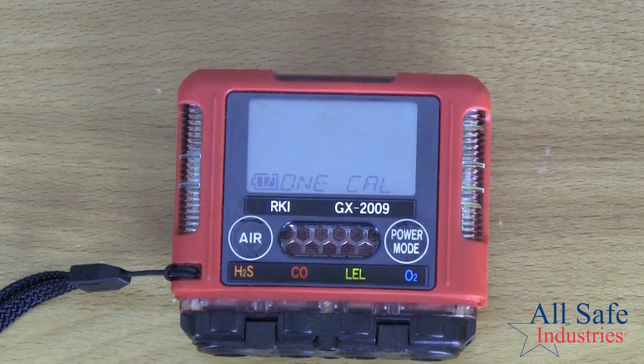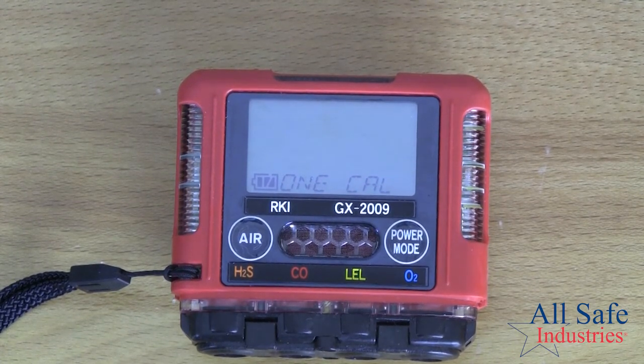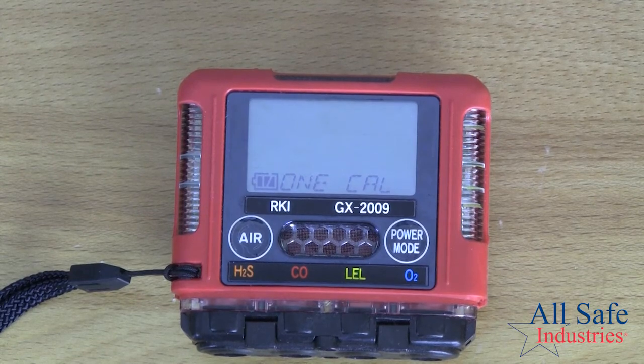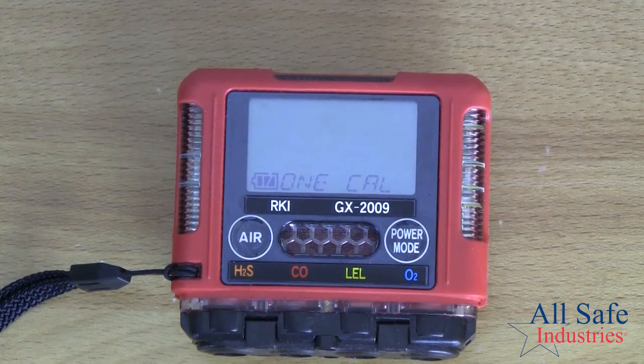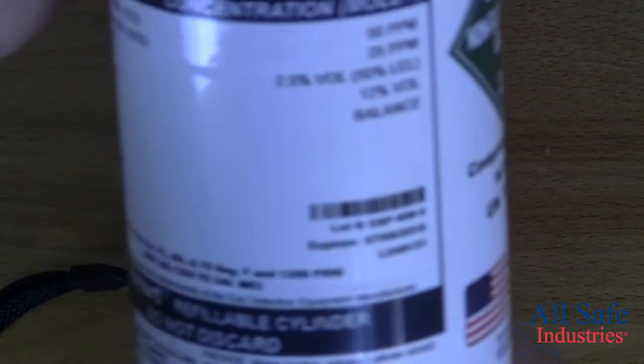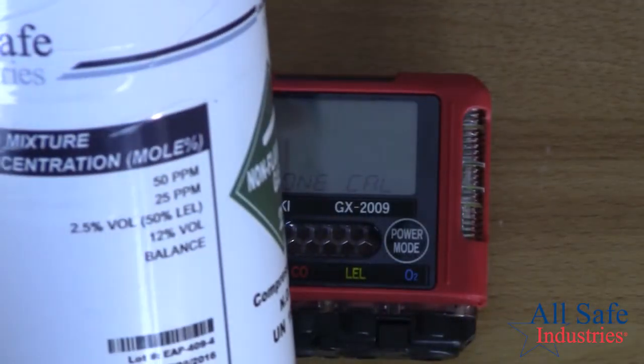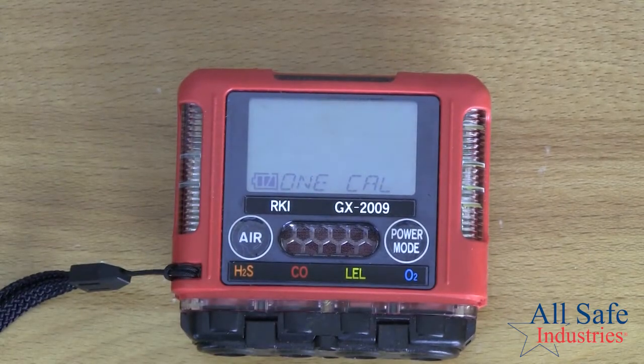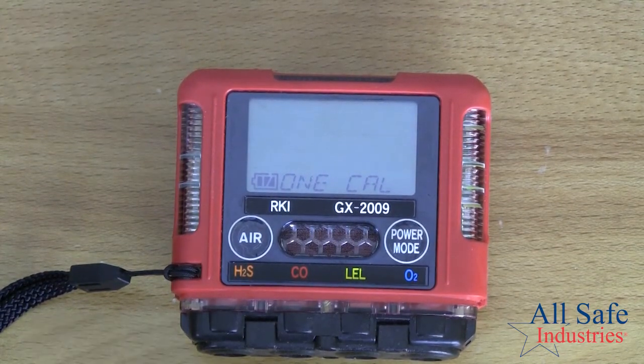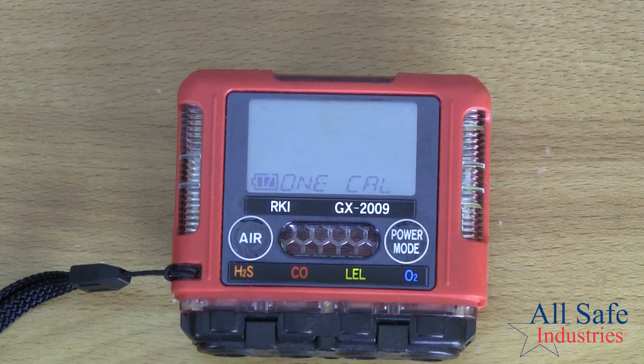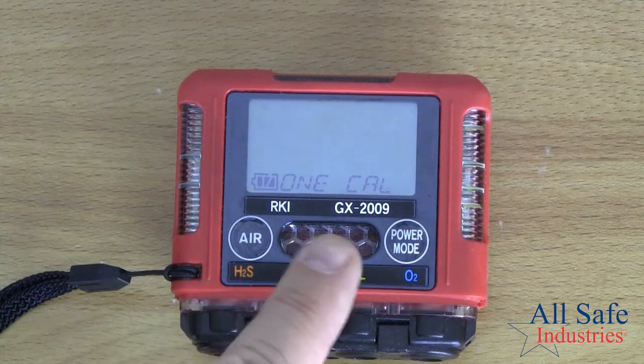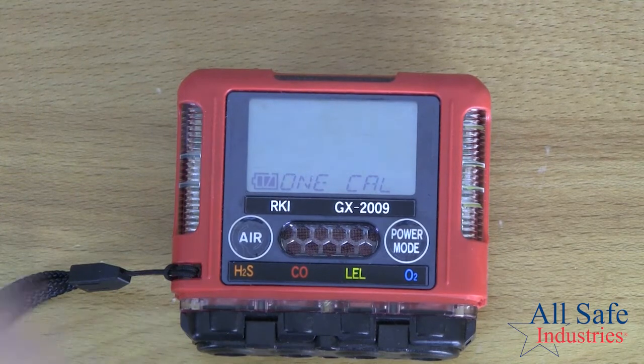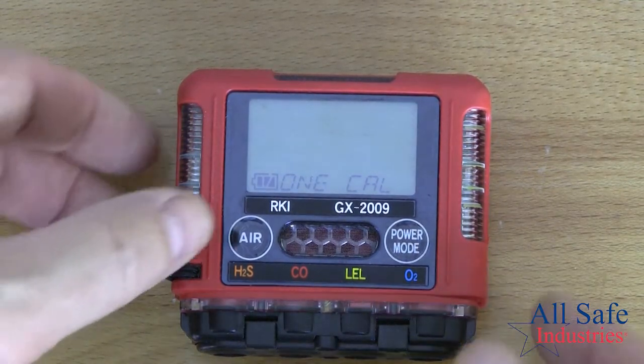Now the one cal is used if all I want to do is calibrate one of the sensors. However, all of my gases are in this cylinder. And so I might as well just go ahead and do an auto cal and calibrate all 4 of them, no matter which sensors I'm calibrating. It doesn't really make sense to just calibrate one since all of the gases are in the cylinder anyway. So I would rarely use one cal. I would use the previous menu, which is auto cal.